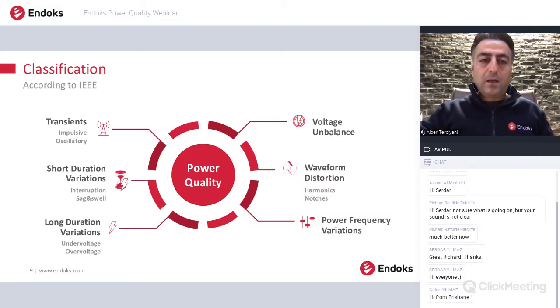According to IEEE 1159, and also some in IEEE 519, we have some parameters defining the power quality. The first one is transients. Transients are impulsive or oscillatory waveforms during, for example, capacitor switching, reactor switching, a lightning strike on the power system, or switching of long but unloaded overhead lines. All these impulsive and oscillatory variations on the system we call transients.